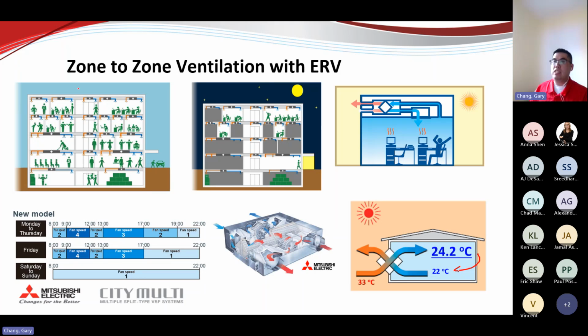And on top of that, you can see this is a pretty good chart. Let's say a building in the morning or during the daytime, everybody's in the office, but sometimes we have guests from overseas, we have auditors and all that, accountants, etc. They may be working a little bit late. So in those cases, we don't have to provide fresh air to the entire building. We just have zone-to-zone ventilation for each zone that requires the minimum or the recommended fresh air value for each zone. And on top of that, we're able to have different fan speeds. Perhaps it can be on time, it can be on occupancy, and on CO2.